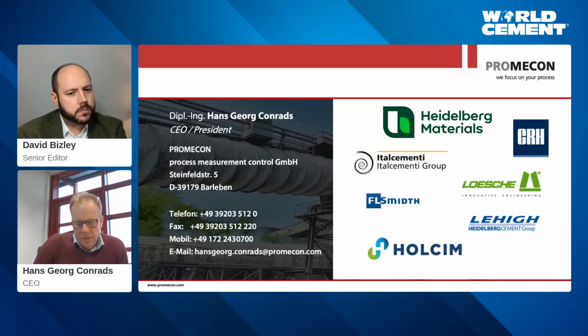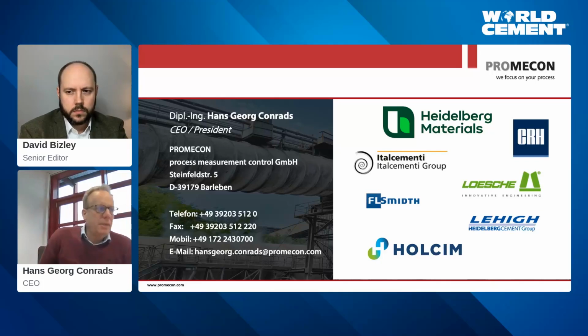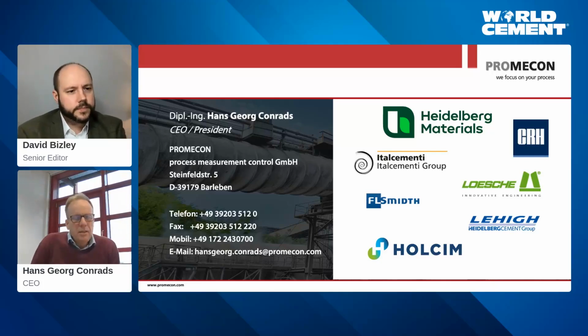So we have several plants where we have now installed what we call an infrared sensor, which I was not talking about today, but I'll be happy to do so on the next webinar. It's a fairly new development. An infrared sensor basically does not protrude into the duct. It just looks from the outside, and it correlates the infrared light the same way that the electrostatic sensor does. And we have installed that in a couple of plants now, and of course there is absolutely no wear issue with that.